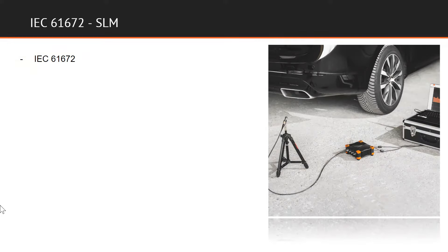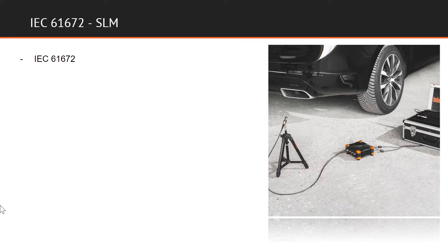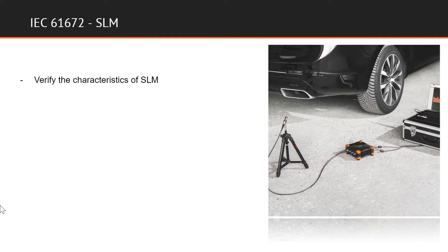As we have established the meaning and importance of performing calibration itself, let's focus next on particular calibration procedures and their corresponding standards. We will begin with one of the most widely used and performed calibration services: class one sound level meter calibration of the measurement chain according to IEC 61672. IEC 61672 is the standard most often used when it comes to calibration of sound level meters. Procedures include tolerances and are designed to verify that the characteristics of the sound level meter are correct.